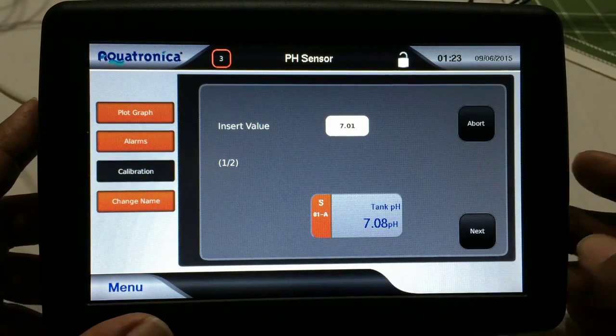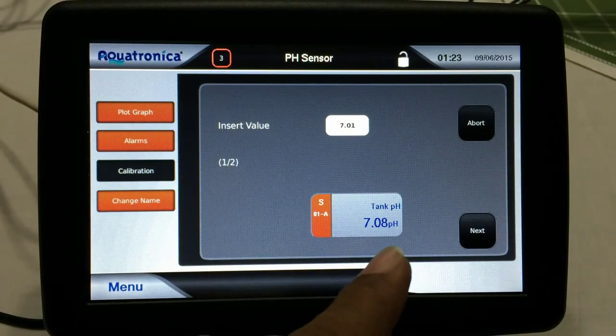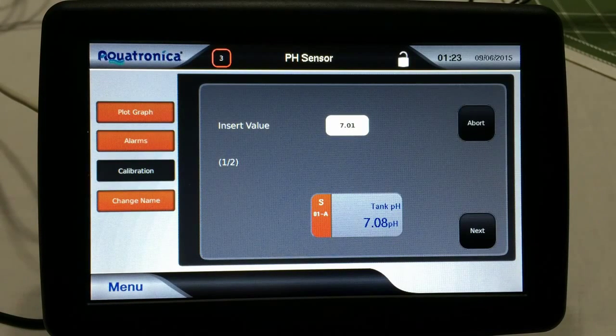And what you would normally do here is let this settle for a while, but since this has already been sitting in this fluid for 5 minutes, and that's why I did it, I don't have to wait too long here. It'll settle right away. If I didn't do that, what you'd probably see is it fluctuating around for about 3 to 4 minutes before it started to settle. So it's pretty much going to be settled already on that value.